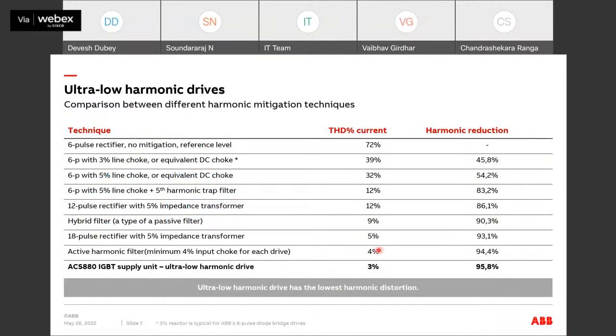Now, I will just touch upon how the harmonics are reduced by the different techniques available in the market. When you talk about a 6-pulse rectifier with no line choke or anything added over it, the harmonics level will be in the range of 72%. When you add a line choke or an equivalent DC choke, the harmonics reduction happens. It can come down to 39%, 32%, 12% with the addition of line chokes.